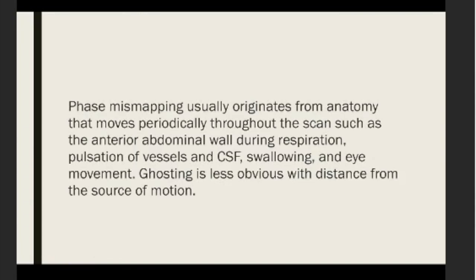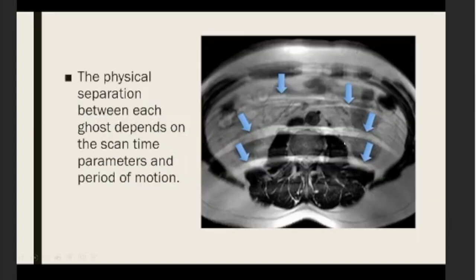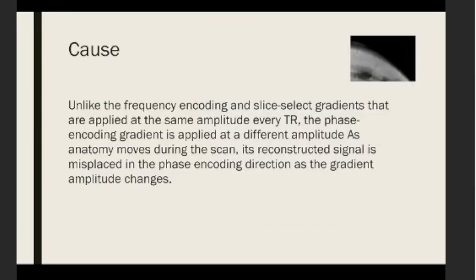Phase mismapping usually comes from anatomy that moves periodically throughout the scan, such as the anterior abdominal wall during respiration, pulsation from vessels and CSF flow, and eye movement — all of these produce ghosting artifacts. Ghosting is less obvious with distance from the source of motion. The physical separation between each ghost depends on scan time parameters and the period of motion.